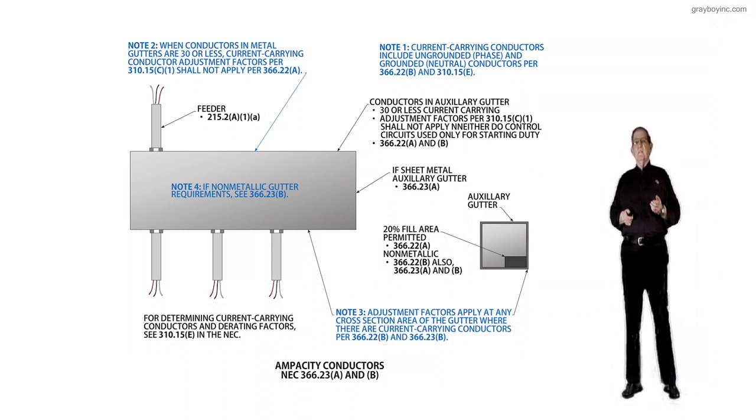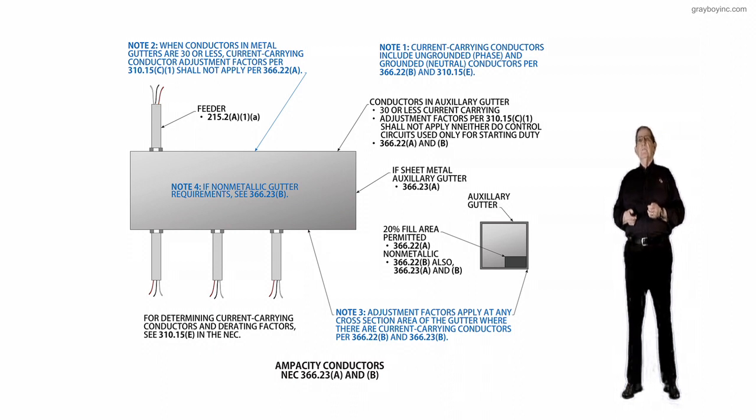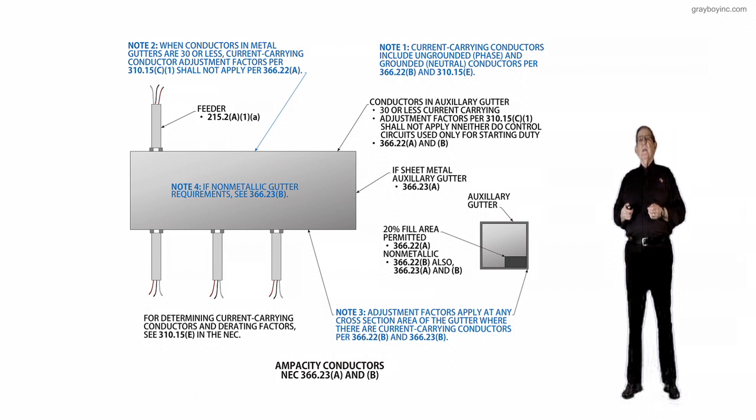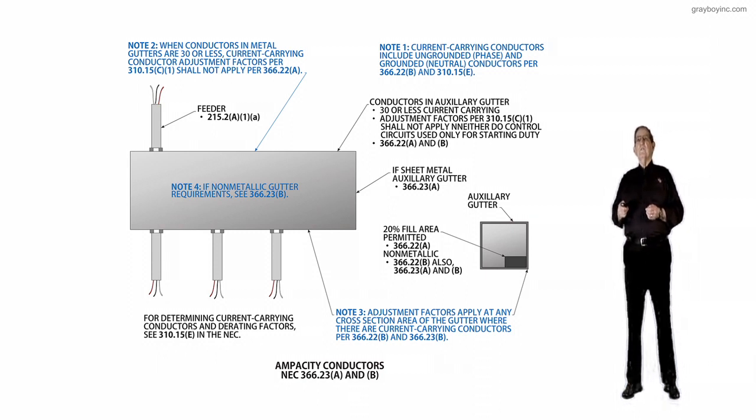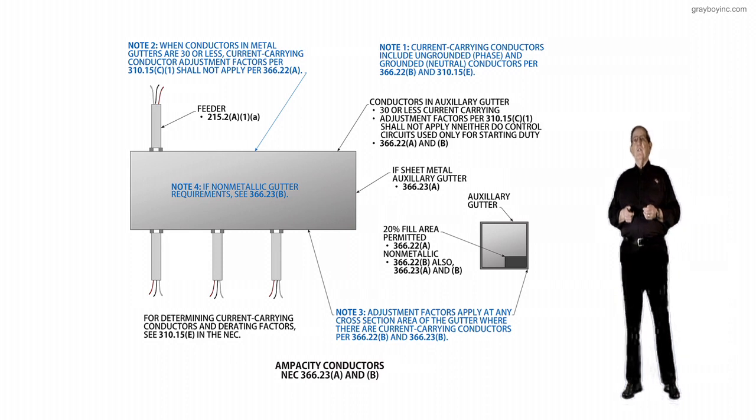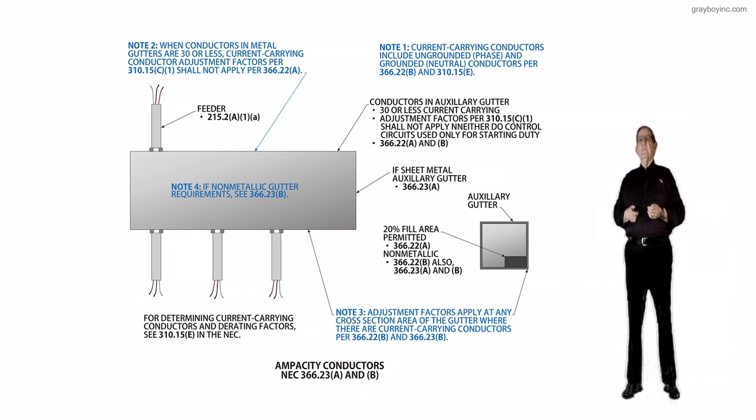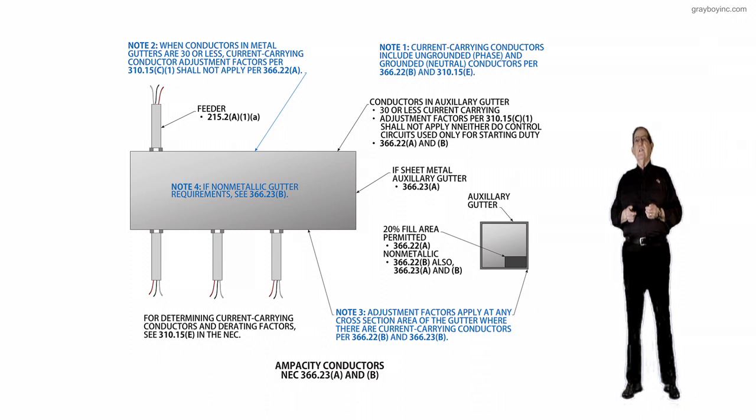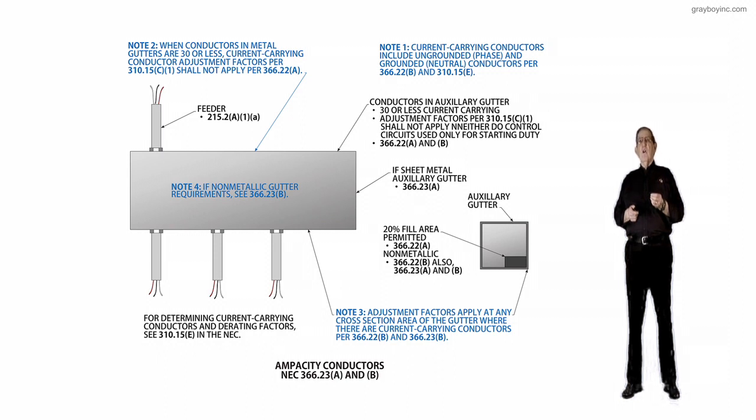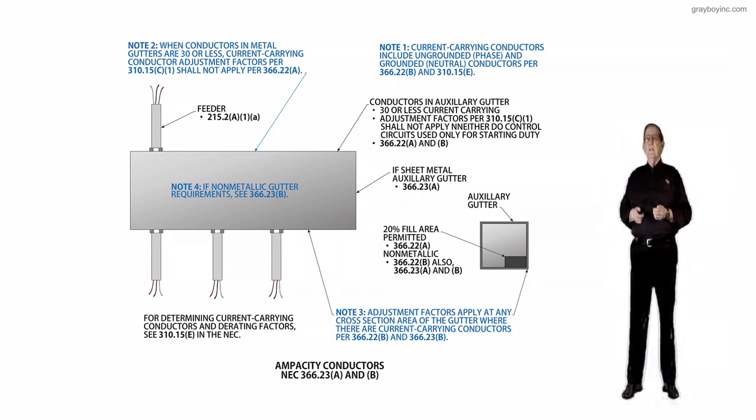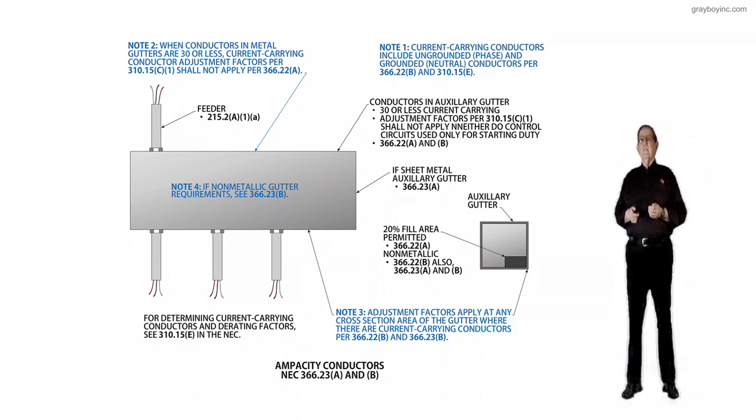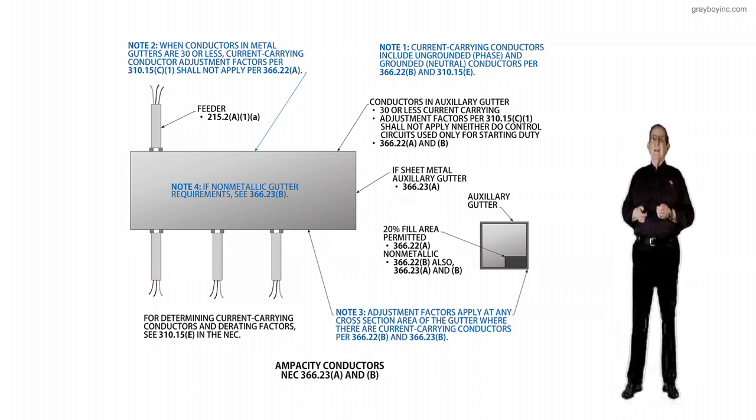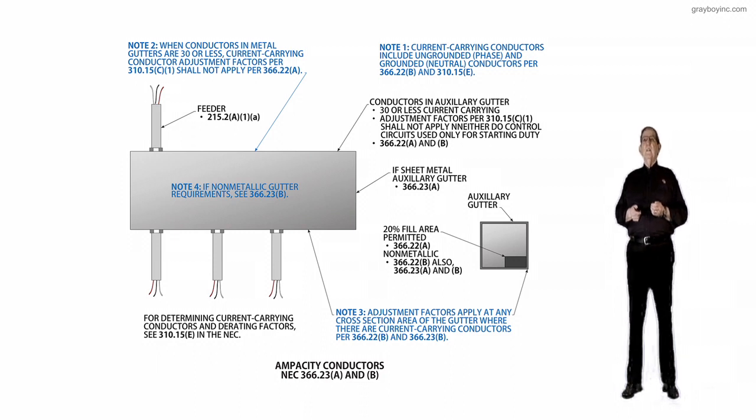But this is an auxiliary gutter, so the call out right above it with the arrow pointing to the auxiliary gutter: conductors in auxiliary gutter 30 or less current carrying, adjustment factors for 310.15C1 shall not apply, and neither do control circuits used only for starting duty. Now make note of that, only for starting duty, allowing a motor to start and accelerate its load.